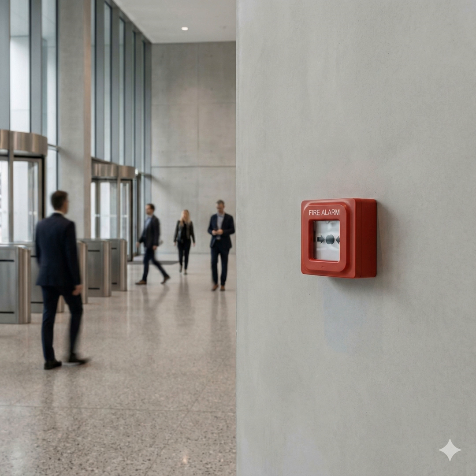And finally, what happens when the system must be temporarily disabled for maintenance or repairs? We have to discuss the impairment procedures. NFPA 72 mandates a highly structured, documented impairment procedure. You have to notify the local fire department. And crucially, you have to implement compensating measures. The most common being a fire watch. A fire watch. A trained individual tasked with continuously monitoring the area and providing manual notification if there's a fire. The documentation tracks the exact duration of the impairment, which is vital for both regulatory review and liability protection.